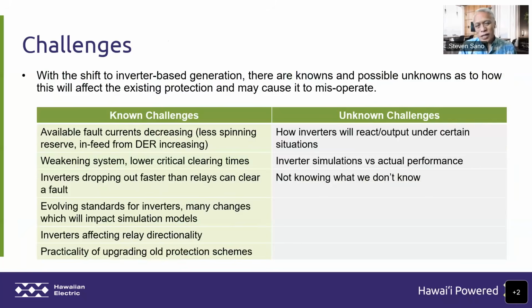Okay, so that's our protection systems based on the past, how our system evolved through our rotating synchronous generation on our transmission and then down to our distribution. These are the challenges that we are currently seeing with the shift to inverter-based generation. There are knowns and possibly unknowns as to how inverter-based generation will affect our existing protection schemes. And there's always the concern that it may misoperate. Our protection schemes could misoperate.